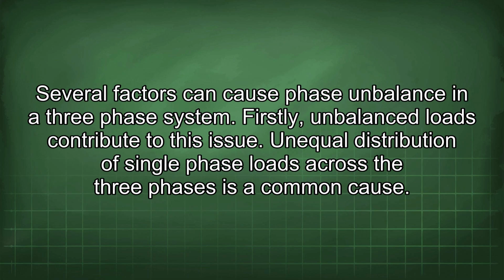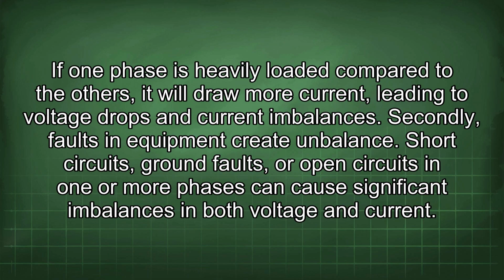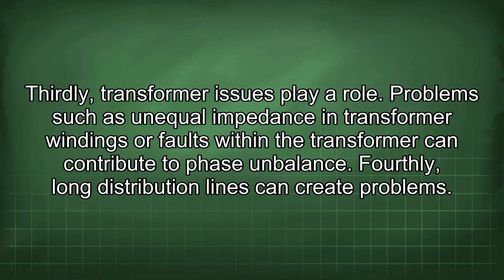Several factors can cause phase imbalance in a three-phase system. Firstly, unbalanced loads contribute to this issue. Unequal distribution of single-phase loads across the three phases is a common cause. If one phase is heavily loaded compared to the others, it will draw more current, leading to voltage drops and current imbalances. Secondly, faults in equipment create imbalance. Short circuits, ground faults, or open circuits in one or more phases can cause significant imbalances in both voltage and current.